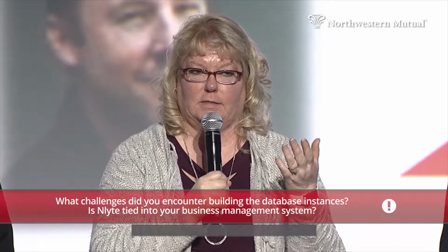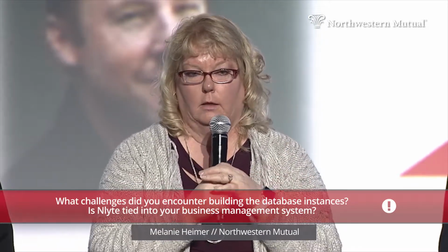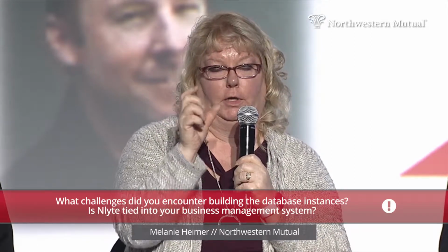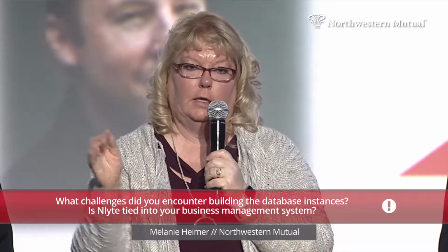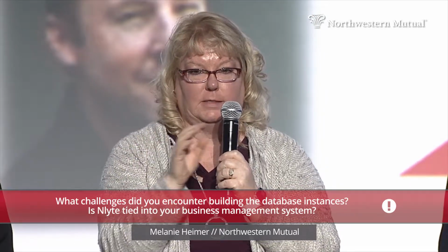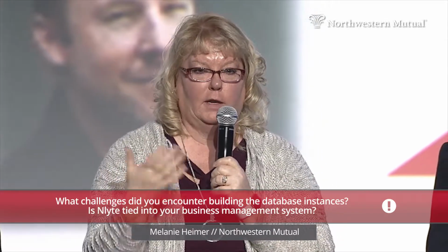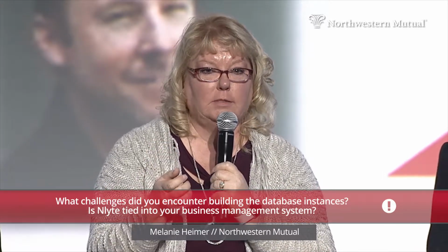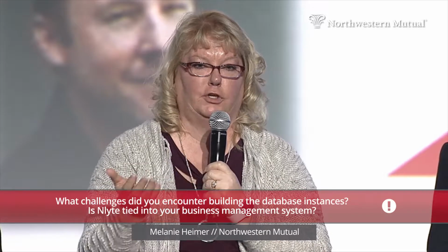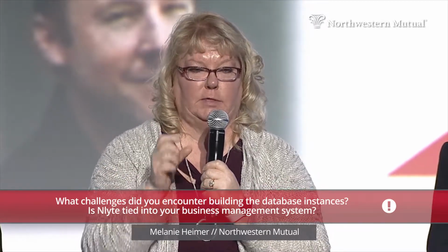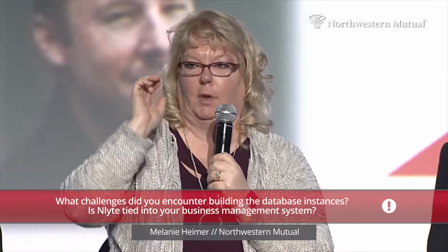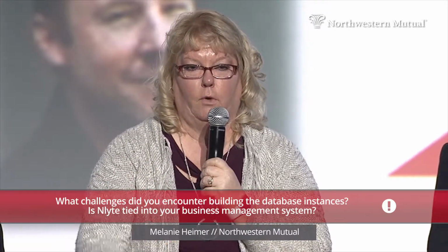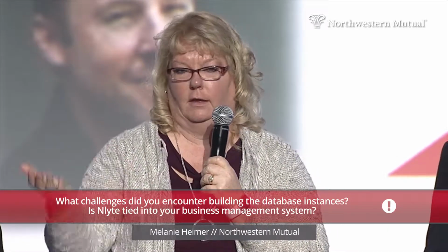The first part of the question, the biggest challenge in building the data, is making sure that everybody does the data the same way. When you're looking at even a server, do you put HP, DL380, or do you put Cisco and the name of the model? Some people would put the model and then Cisco. Some people didn't put the maker at all. When you go to import it, that all matters. So it's getting everyone on the same page, doing things the same way. Even though we talked about it and thought we were doing it the same way, people understood that differently. So spend the time, maybe doing a small sample, instead of letting them go and spend a whole 4 hours doing a whole bunch of racks that are different than the next person's.